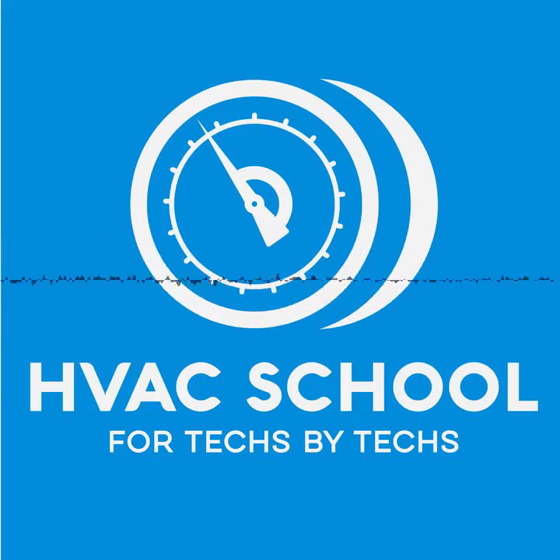With variable speed, take that dry bulb stat out of the picture, put one that measures both latent and sensible heat, and run your system to focus on the air treatment that's required. And that's really about as far as we can go with residential systems.